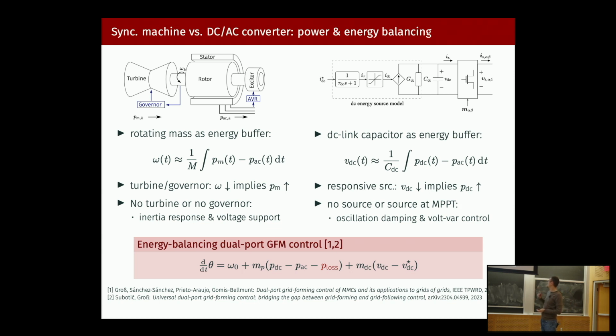And this is basically what I'm proposing here. So if you look at the machine, in fact, it doesn't do any of that stabilization and droop control we were talking about - this all comes from the turbine. The machine is basically taking an electric power imbalance, turns that into a mechanical frequency, and if that deviates, then something responds.